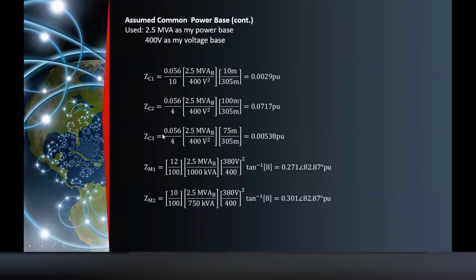Okay? Next, equipment. We are done with cable 1, cable 2, cable 3, utility, and transformer. Two left, which are motor 1 and motor 2. Okay? For motor 1, they said it has a subtransient reactance of 12 during the half cycle. So 12 divided by 100 because you are making it per unit, multiplied by MVA base, divided by 1,000 horsepower. We said earlier, 1 horsepower is 1 kVA, which is the safe assumption according to IEEE.